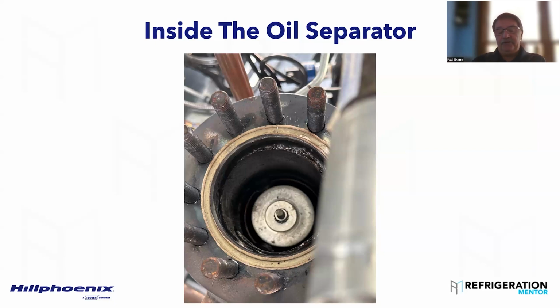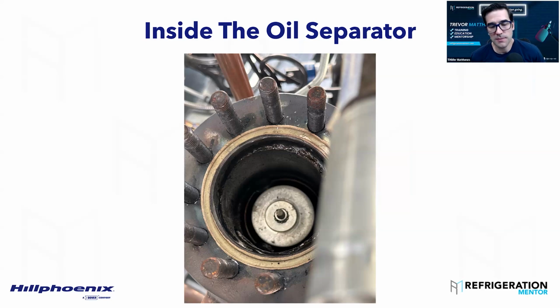The reason I put this in here is when you start that rack up and you have 24-hour continuous operation, within 2 days to a week, you're going to want to go through and change that separator filter. You're going to want to change your suction line filters, and clean out your filter dryers. I apologize, your inline filters. You want to take the supply lines apart, make sure that they're clean. Yeah, because there's going to be dirt in the system. We try our best to keep it as clean as possible, but we're talking about thousands and thousands of feet of pipe. Some people are not as skilled as others, not as clean. I've done it.